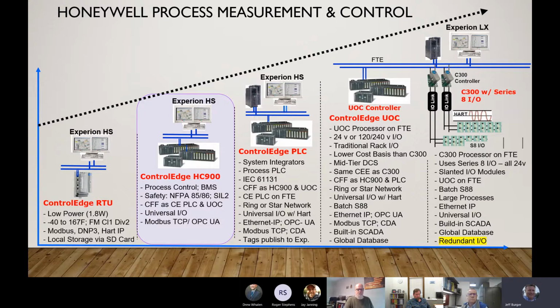The next step would be the ControlEdge PLC if we're moving to the right. The ControlEdge PLC utilizes the same rack and I/O cards as the HC900, but allows you to program it in ladder logic, sequential control, or function block, and offers a nice transition for customers that are going from an older PLC upgrading to a newer PLC, and it operates in that PLC environment with doing very fast discrete control.